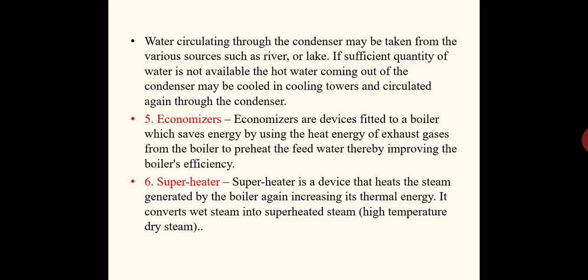After producing the steam, the wet steam will be passing through the superheater. There further heating will be taking place. That means wet content will be removed and the temperature of the steam will be increased. Superheated steam means corresponding to pressure there will be a saturation temperature. Heating above that saturation temperature is known as superheating. So, the function of the superheater is to superheat the steam coming from the boiler to the superheat temperature.